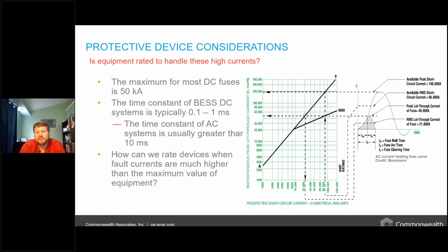So here's an example of what I'm talking about. What we're showing here, credit Bussmann fuses, is a graph for a typical AC application of a current limiting fuse. Our fuse clearing time, the TC in the graph, is basically showing how much time is going to pass before that fuse totally clears the fault.